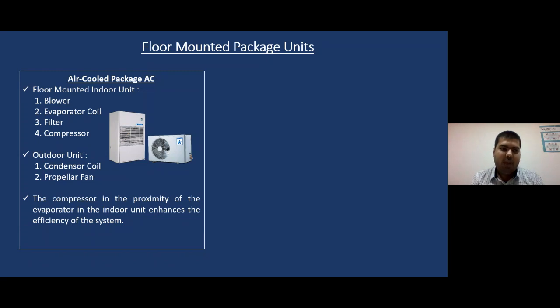So in my air-cooled package AC, the indoor unit, that is basically this vertical machine, would have the blower, the evaporator coil, the filter, and the compressor. And my outdoor unit would have a condenser coil and only the propeller fan. Moreover, the beauty of it is there is no piping duration to it. My compressor and my indoor unit are very close in the same machine. So there is no piping duration, and hence the proximity of the evaporator to the compressor gives better efficiency to the machine. That is why package ACs are most preferred in auditoriums and theater applications.